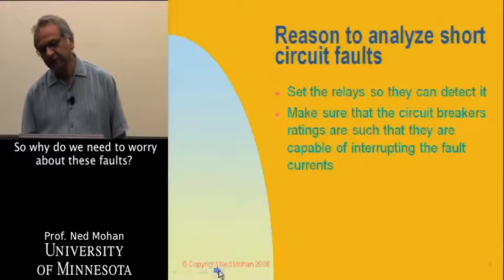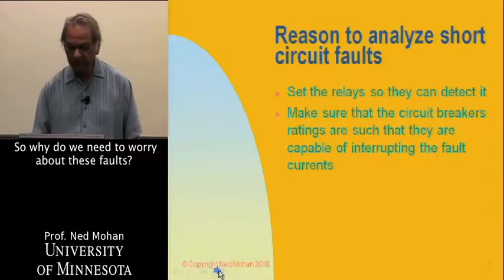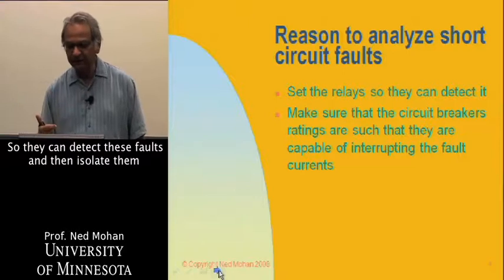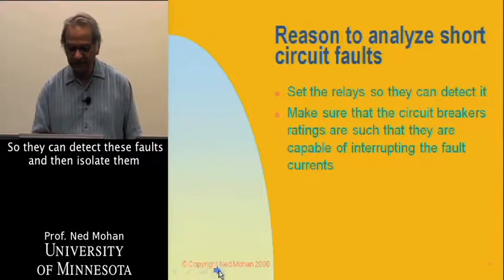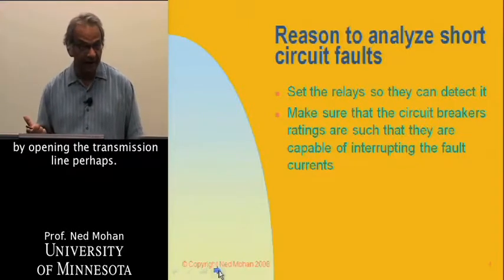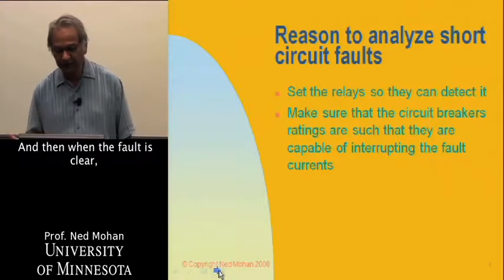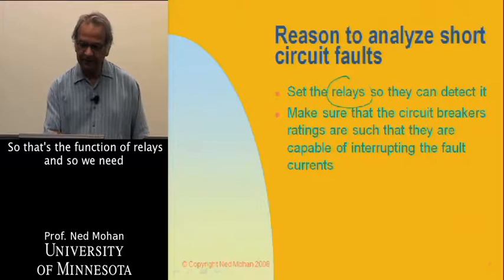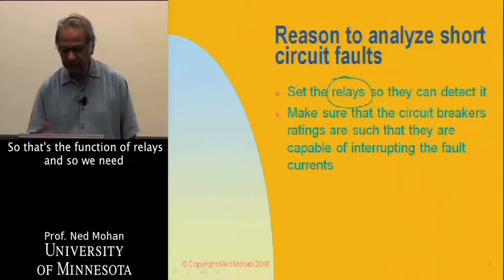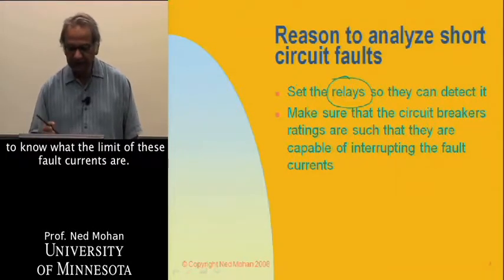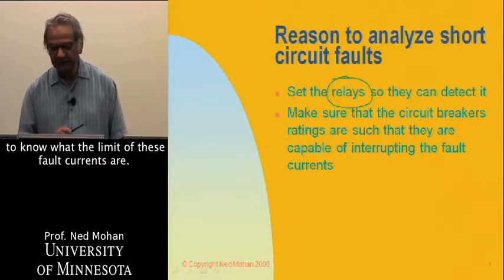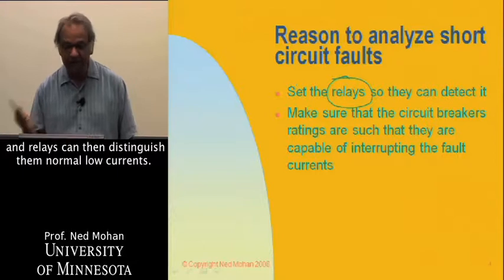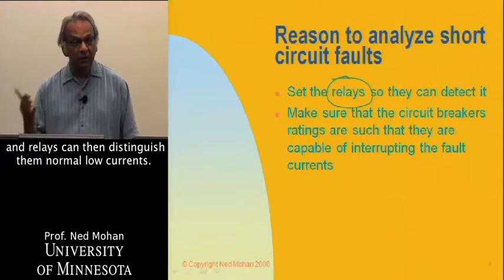Why do we need to worry about these faults? First of all, we need to set relays so they can detect these faults and then isolate them by opening the transmission line. When the fault is clear, reclosing the transmission lines. That's the function of relays. We need to know what the limit of these fault currents are so we can properly set them, and relays can then distinguish them with normal load currents.